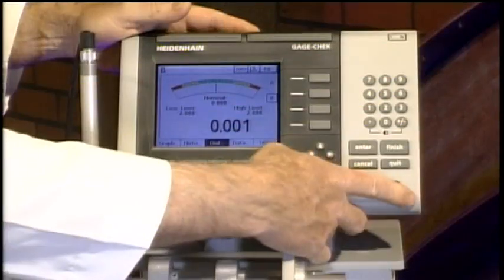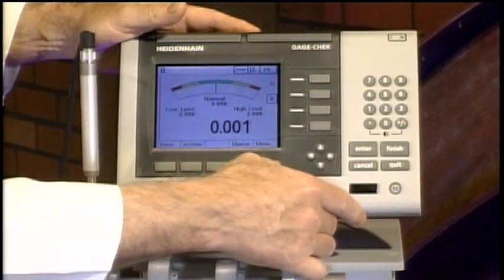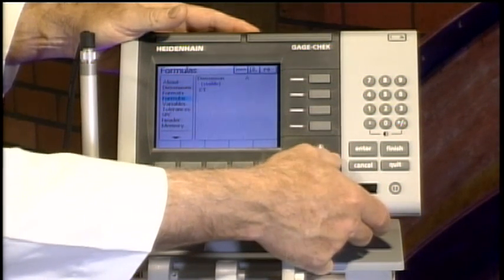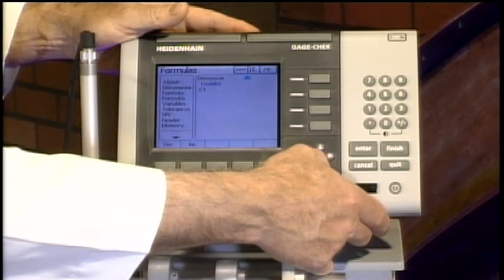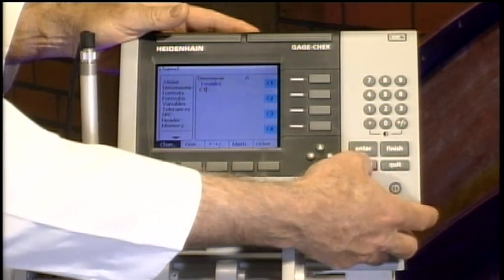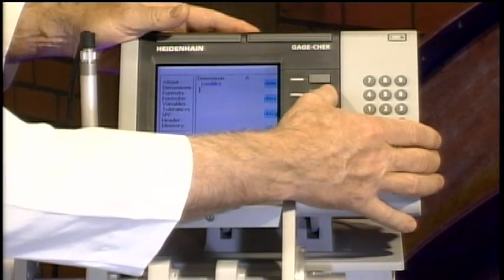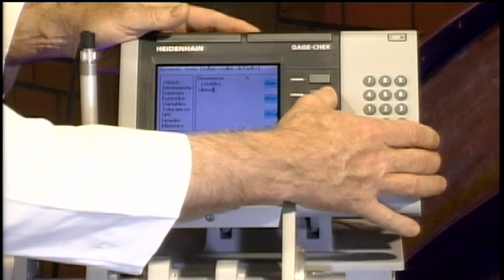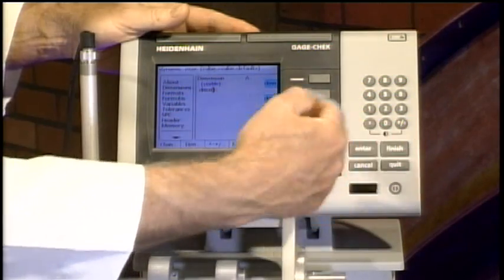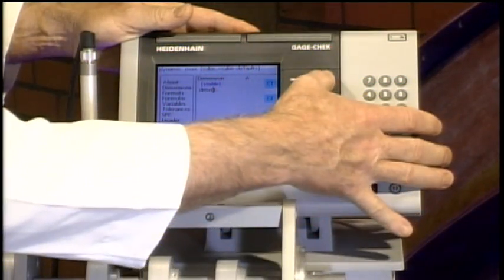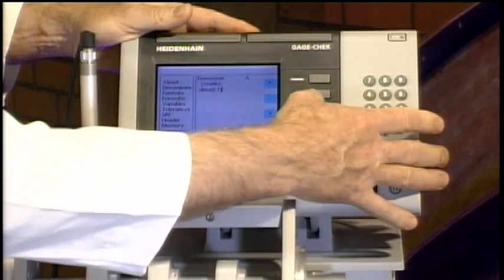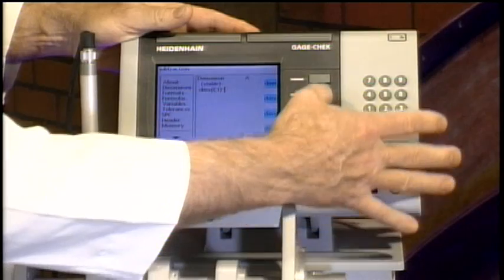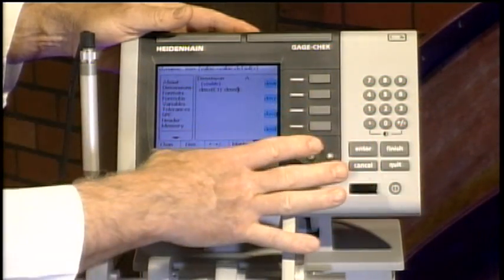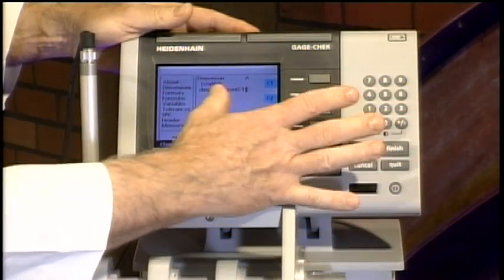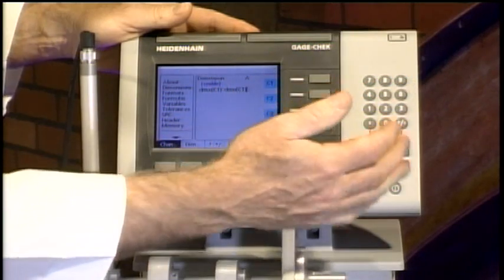So we would come over here. I would go into my menu, and we'll go into Setup. I'm going to scroll down to Formulas. I'm going to create a formula for my A measurement. I'm going to delete what I already have in there. And let's program in the first thing: find my maximum measurement. This is dynamic, so it's looking for the maximum value from the gauge continuously. I want to look at my channel 1 gauge, and I'm going to subtract from that the minimum value that it finds on that same gauge. So now my formula essentially is my maximum value that I find minus my minimum value that I find. That is going to be my run out.